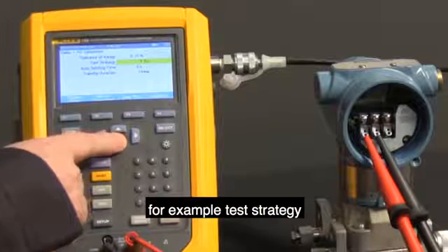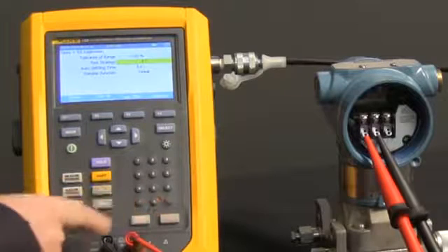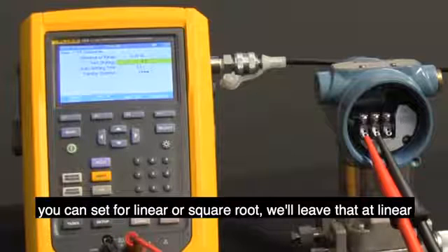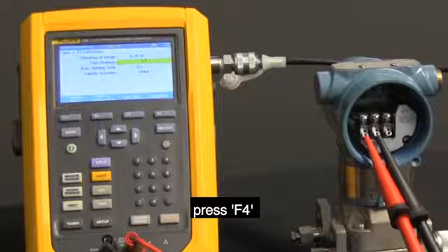For example, Test Strategy, we're going to select 3 up. Auto Settling Time, we'll leave at 5 seconds. In the transfer function, you can have set for linear or square root. We'll leave that at linear. Press F4.